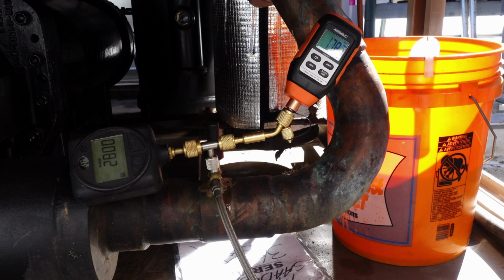Be careful that it's not somewhere close to your oil side. You don't want to hook up anywhere that's directly connected to your oil separator, because you run a lot of risk of drawing oil into your evacuation pump or into your gauge.